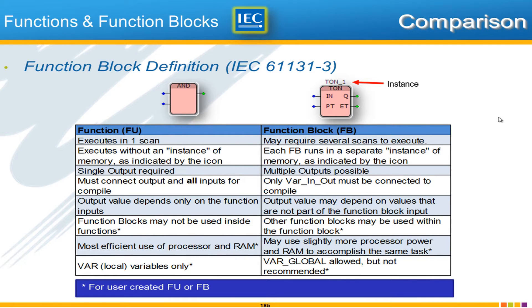Let's start with a comparison of functions versus function blocks, using an example of AND and TON, two blocks we've used. The first distinction of an IEC 61131 function versus function block is that every single function will execute in one scan — one scan through the code and the inputs produce the output. This is not necessarily the case with a function block. Think of the block TON: several scans are necessary just to tell how much time has gone by.